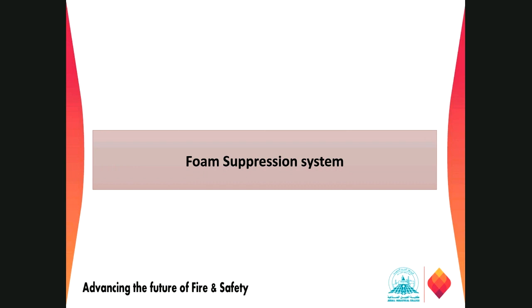So going quickly over all those definitions we discussed in the previous foam systems course also. The expansion, stability, fluidity, contamination resistance, sealing and resealing, knockdown and extinction, and burn back resistance, right? So the expansion means how much finished foam is produced from a foam solution when it is passed over the foam making equipment. How much it expands. Stability means the ability of finished foam to retain its liquid content and to maintain the number, size, and shape of its bubbles. It means how stable it is on the surface of the fire once it goes.